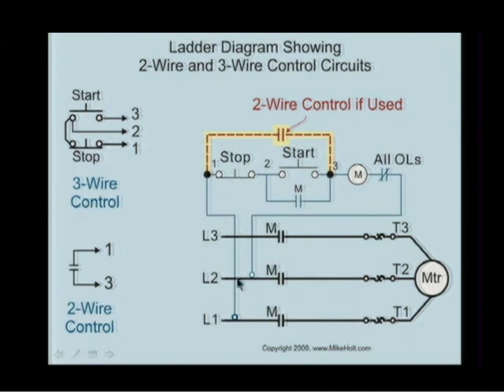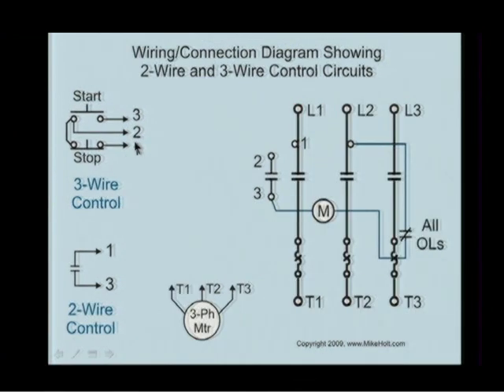Go from line 1 to line 3. That coil is going to operate. And let's see. This line 2 is going to be black because that's already pre-wired. All right. And then here's your 2-wire control circuit, 1 to 3, 1 to 3. Here's the start-stop. That's fine. And I think this is just showing what the wiring diagram would look like inside the actual contactor itself, on the diagram given on that.